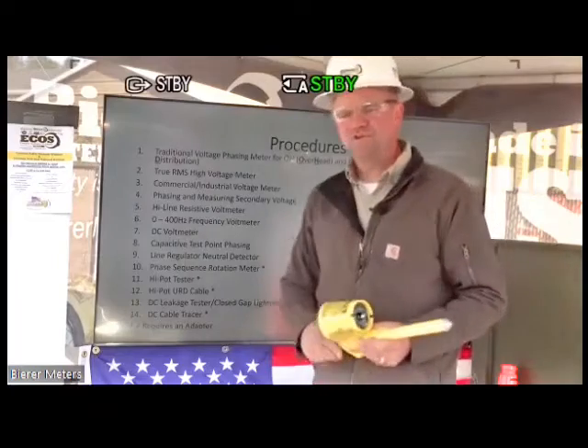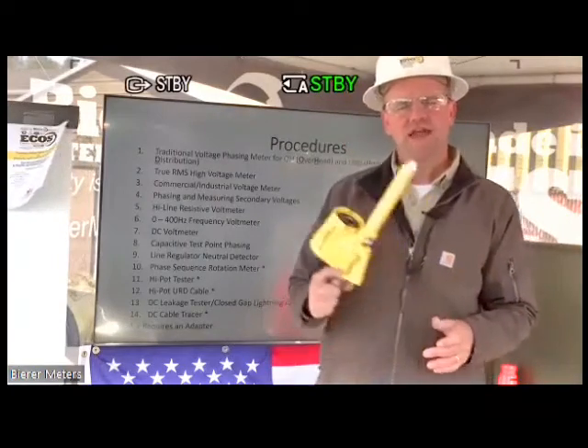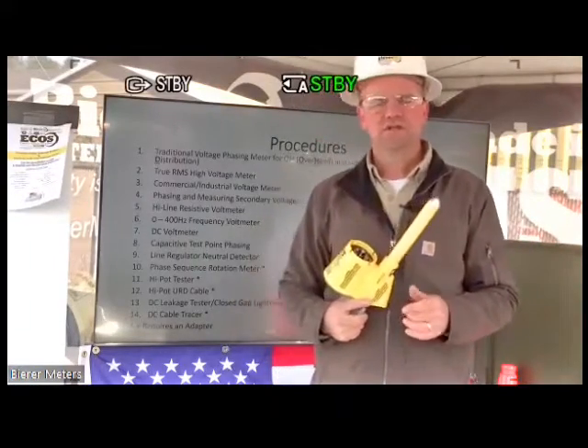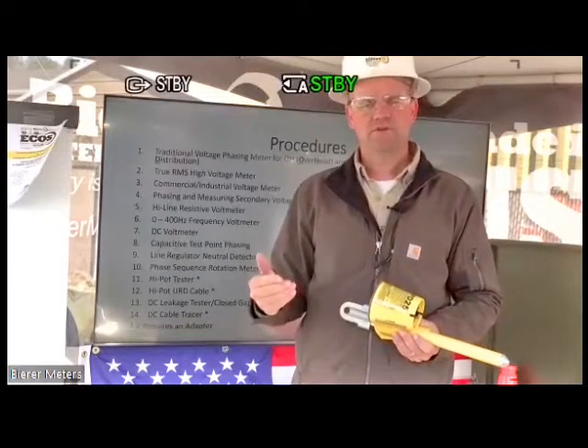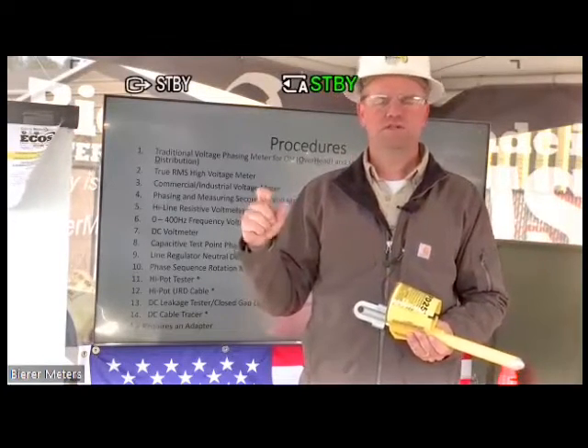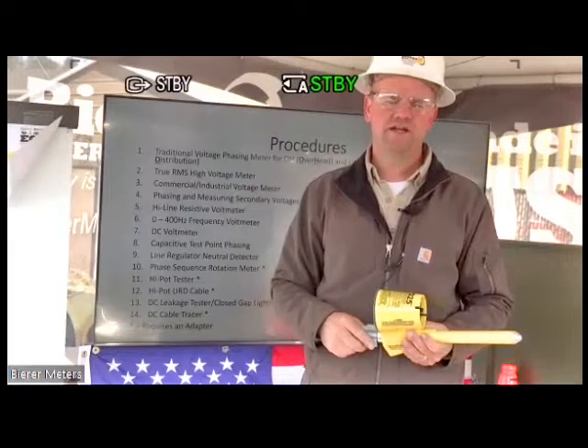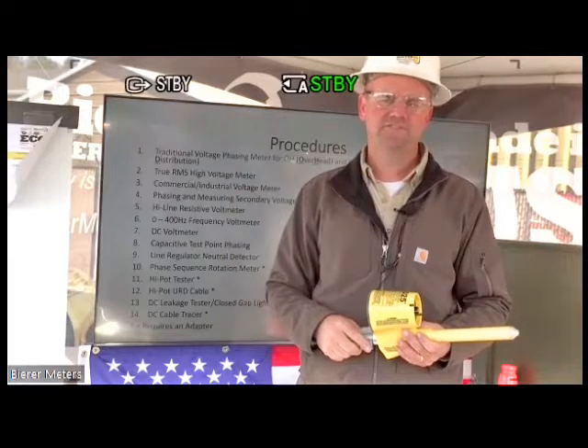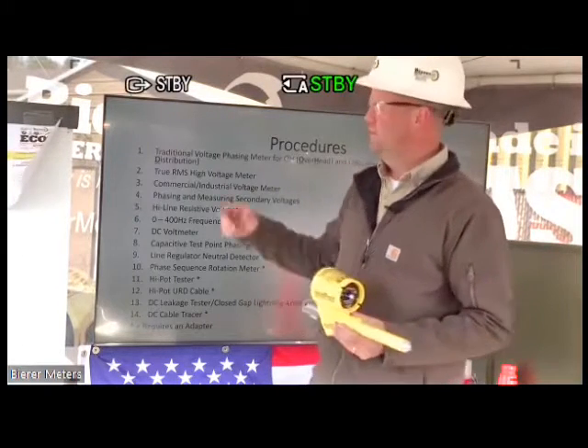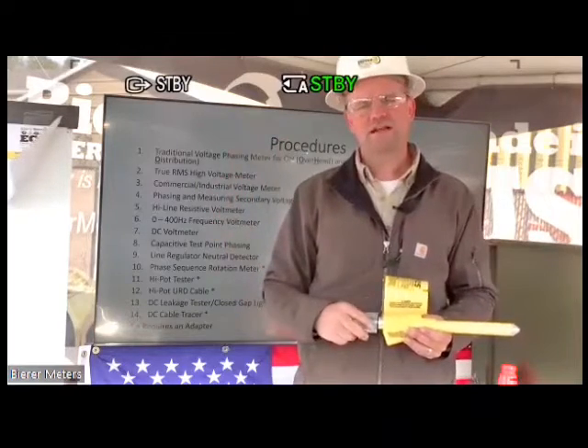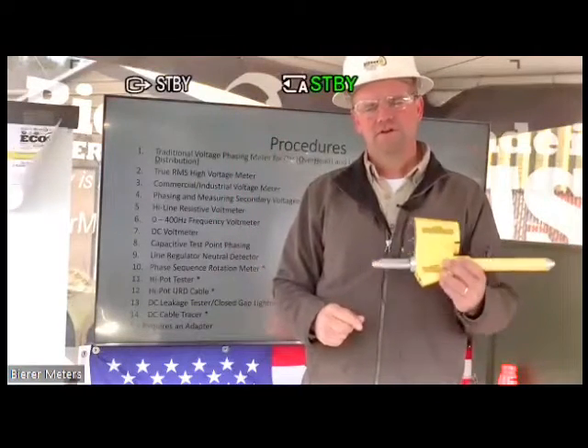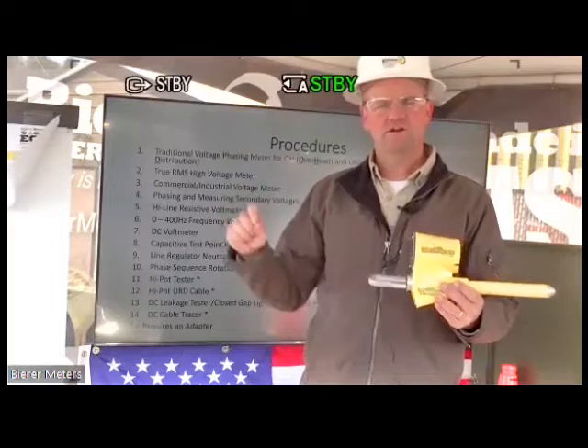A line regulator neutral detector. Again, with the accuracy of this tool, if a regulator is out of step, maybe the dial has broke. It is a mechanical feature of a regulator, so those things can fail. So you can actually determine if a regulator is in step or out of step, versus what the light on it may say.